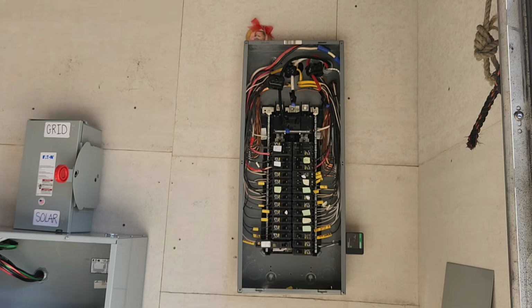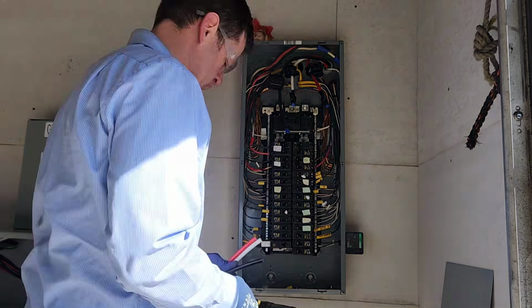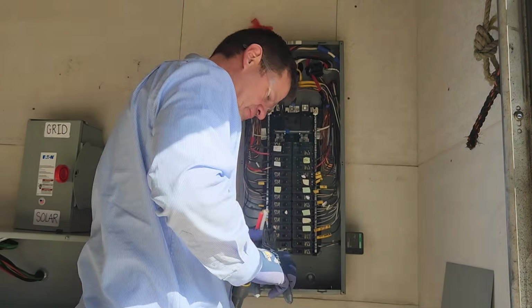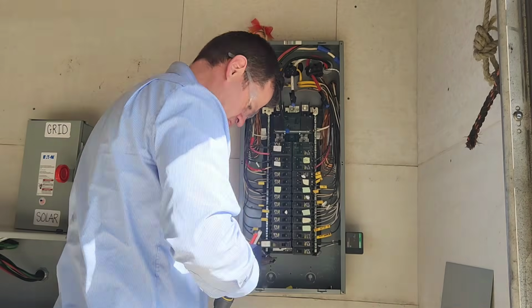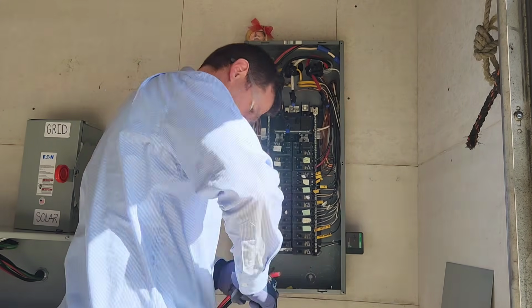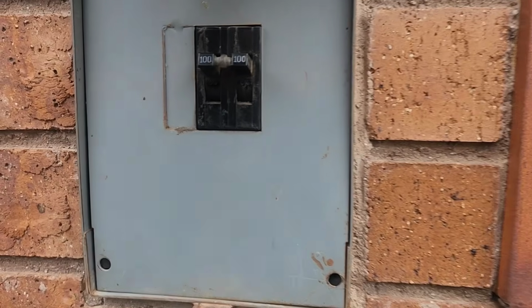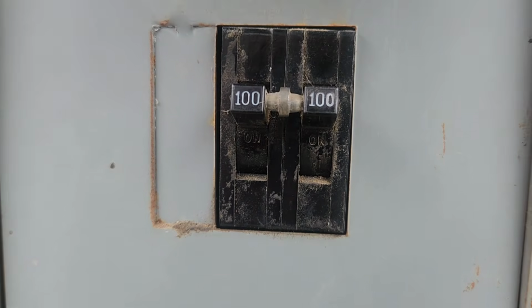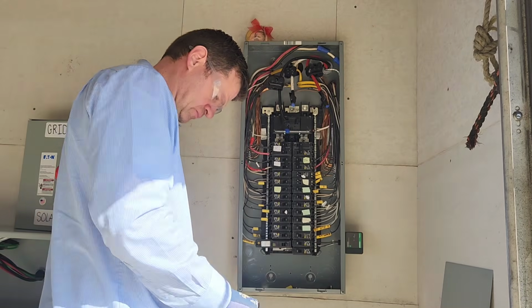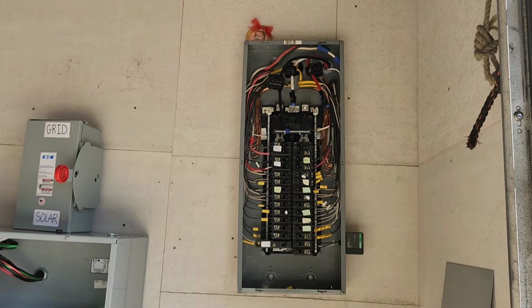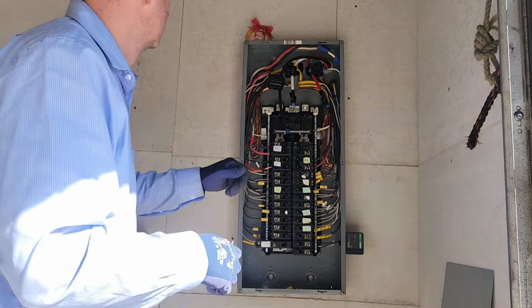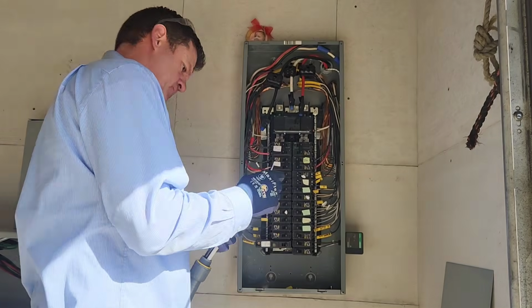If you notice, I have a 200 amp panel with tons of breakers on here, and the conductors leading into this panel are actually 2 gauge. That's because I have 100 amp service outside, so I'm not going to be running 200 amps into this panel. I have a 100 amp double pole breaker outside at my service, so I shouldn't ever get more than 100 amps.